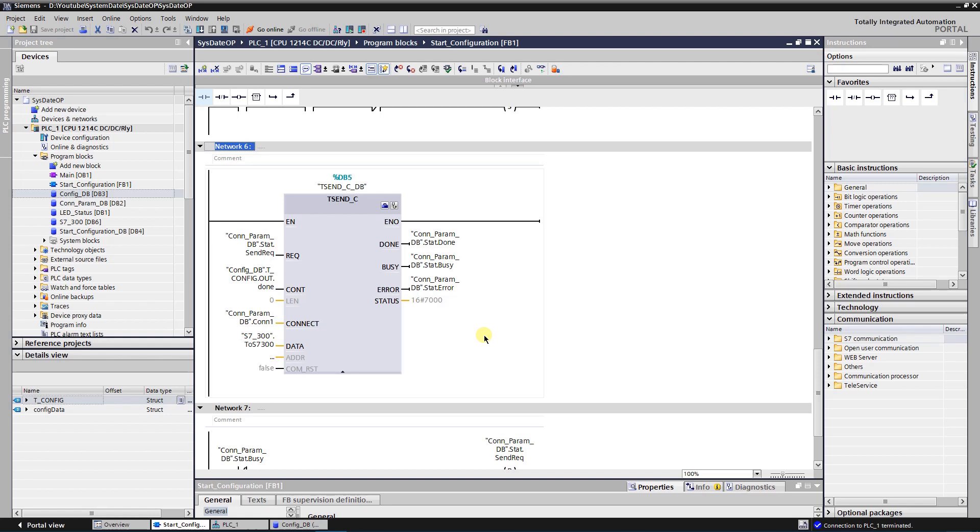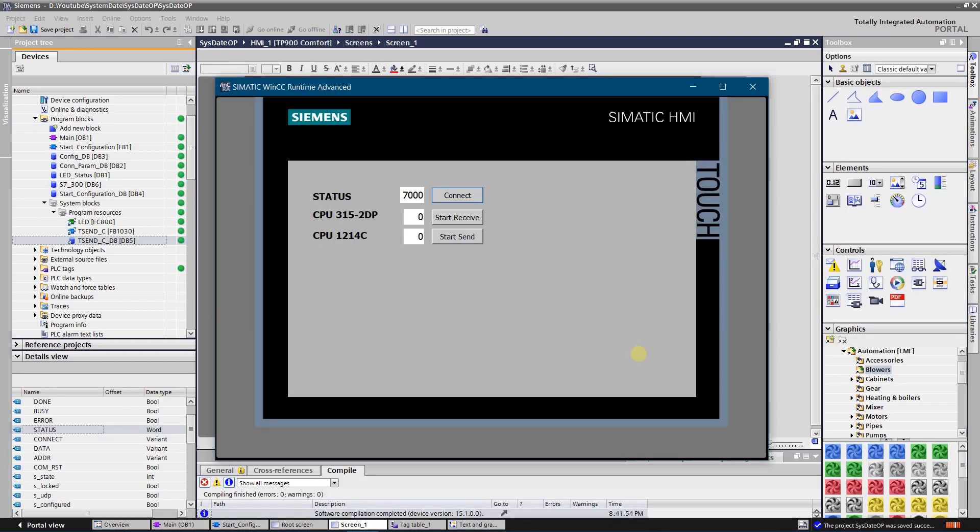Let's try to activate connection between these two CPUs. To activate the connection on the S7-1200 side you need set input CONT of T-Send-C to true. At the moment value of the output status is 7000 in hex. It indicates that no communication connection is established.